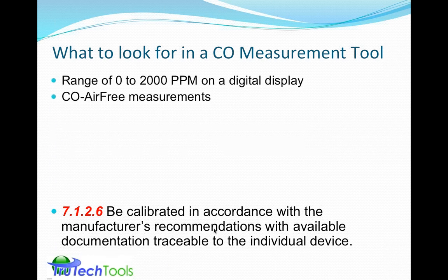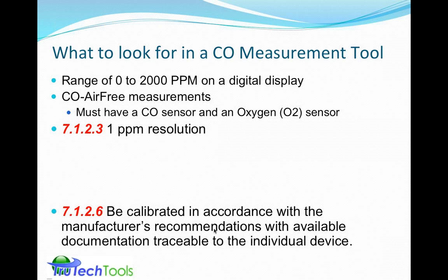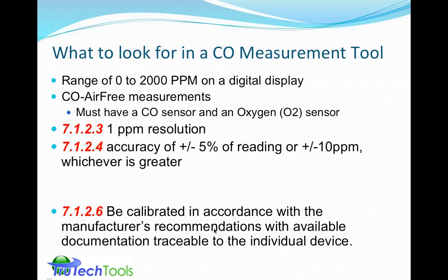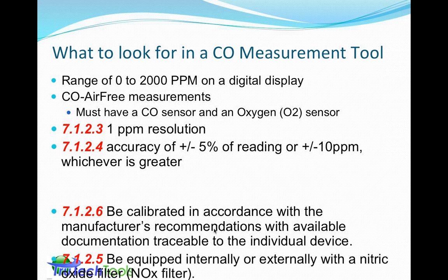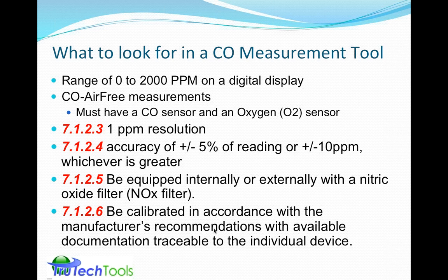This got in a little bit out of order here, but what we're looking for in a CO measurement tool is the range of 0 to 2000 on the digital display. So it must have a display. It must have a CO and oxygen sensor. It has a resolution of 1 part per million and an accuracy of plus or minus 5% of reading or plus or minus 10 ppm, whichever is greater. So that basically puts you in the ballpark of just about every commercially available combustion analyzer at this point that has a CO sensor.